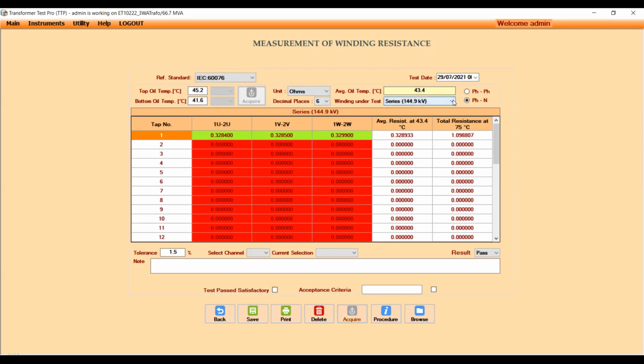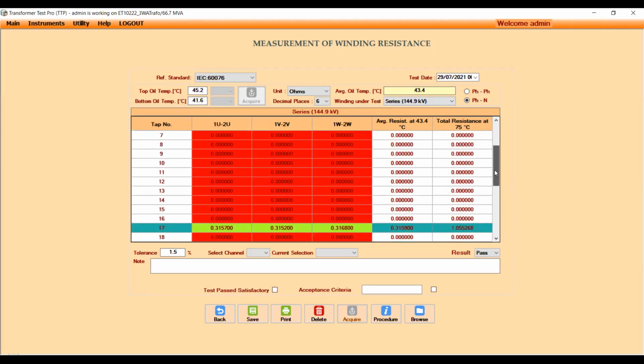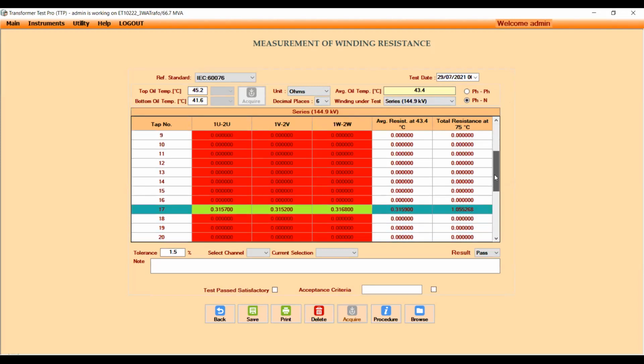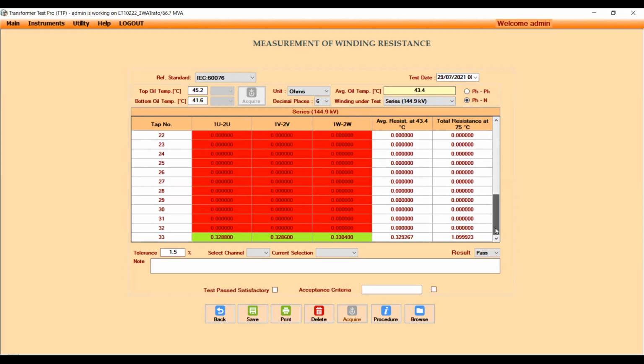You can choose the winding under test. It could be any winding: HV, LV, series, common, tertiary, whatever it is. Then you have the measurement of resistances, whether it is phase to phase or phase to neutral, depending upon the kind of winding resistance meter that you have chosen. Now here the measurement can be done for all taps. It has been done here for tap number 1, then the normal tap at 17, and the last tap at tap number 33.